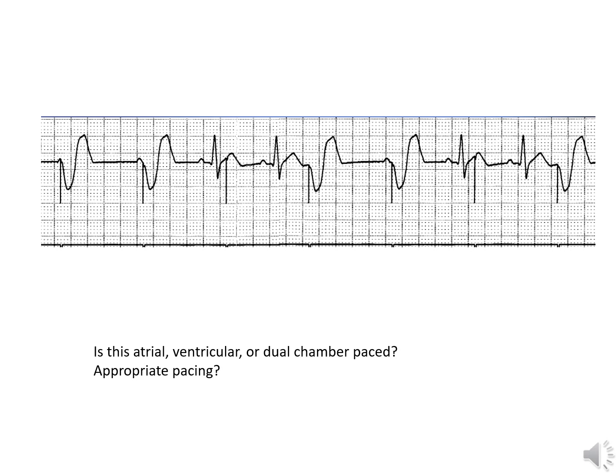So what we want to do is lower the fence so we can see more of what is going on with the patient. So let's say your pacer settings are, the sensitivity is set at a millivolt of 2.0. So what you'll do is adjust your sensitivity to maybe a millivolt of 1.0 or 0.8, and hopefully that should get rid of the inappropriate pacing, and that should help your patient with the sensitivity.